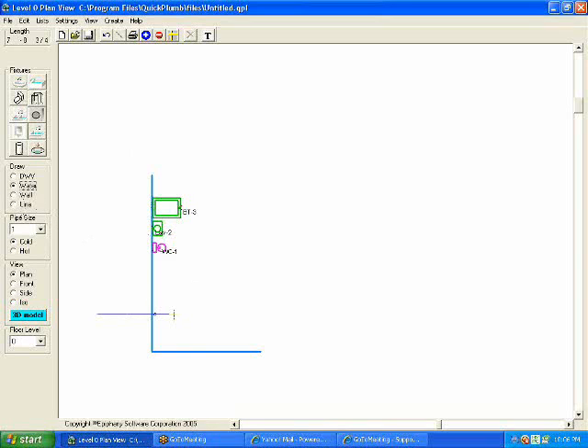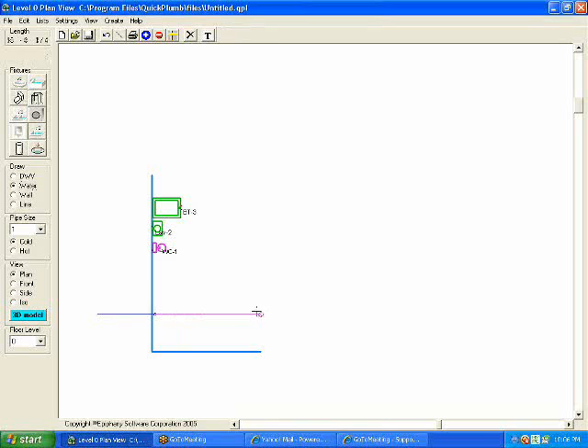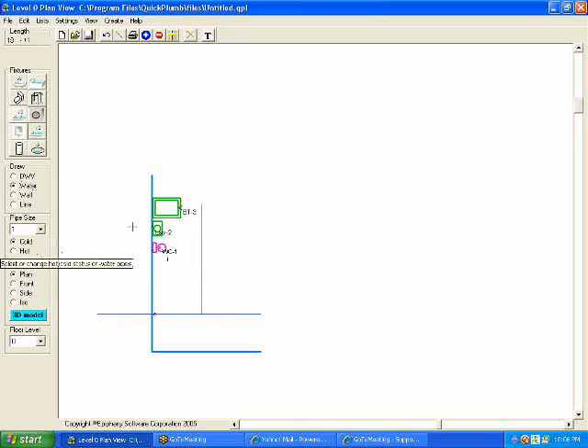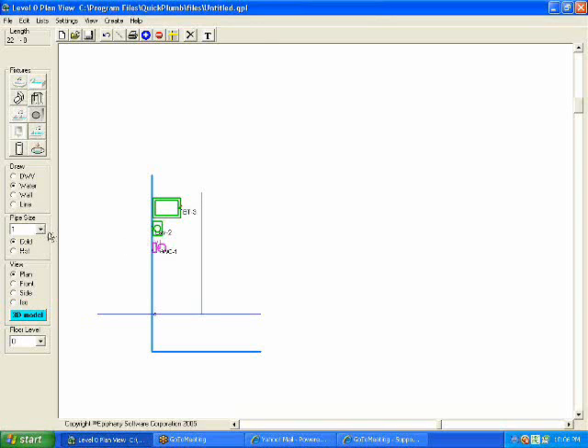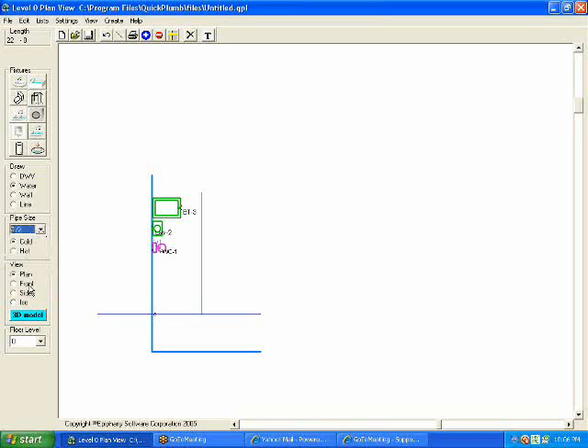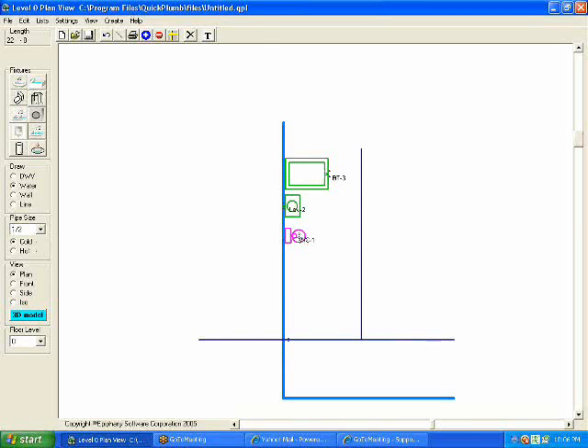Once we've placed the fixtures, we can begin connecting the cold water to the fixtures. Now I'm going to change the pipe size for the individual fixtures. I'll connect my toilet first. A typical residential tank type toilet would use a half inch supply, and it would always be cold. To connect this toilet, all I have to do is click anywhere on the fixture and drag my mouse over.